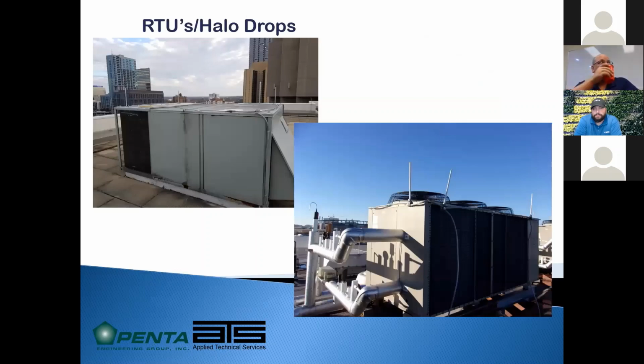So with rooftop units, there are some exceptions in NFPA that allow you to mount metal to metal contact and just have the air terminal mounted directly to the top of the unit with a bonding connection at the base. We prefer to do what we call a halo drop, which basically interconnects the air terminals on top, air terminals within 24 inches of the corners, and then provides it with 2 pathways to ground to the rest of the rooftop system. And this is a unit where, for some reason, these air terminals are side by side and not on each corner. And again, the conductor is not securely fastened every 3 feet.